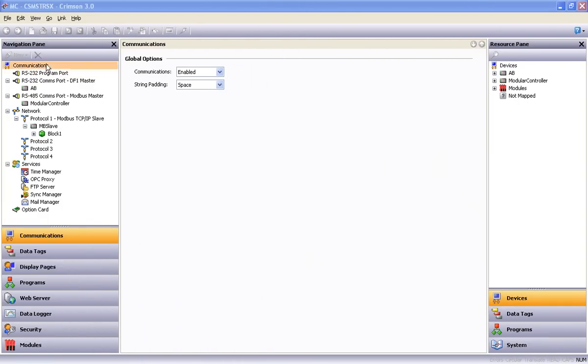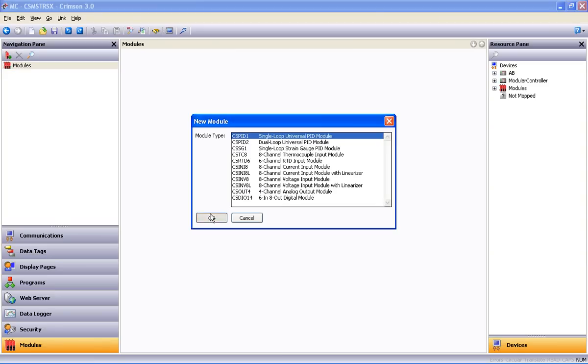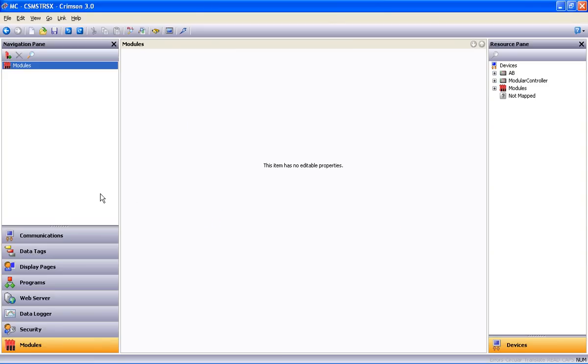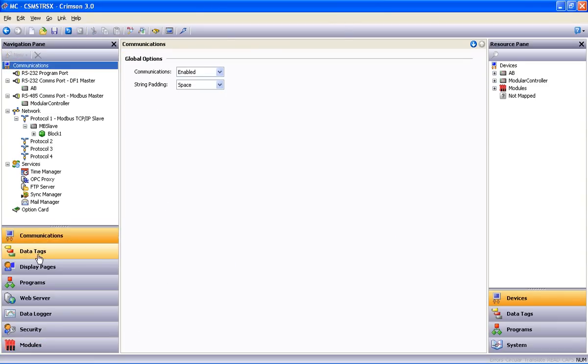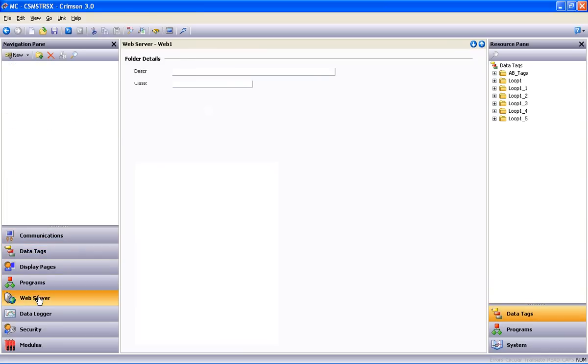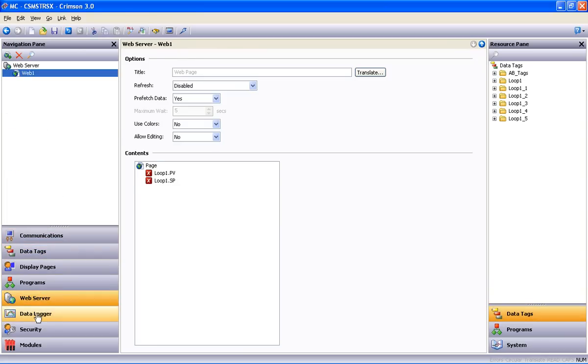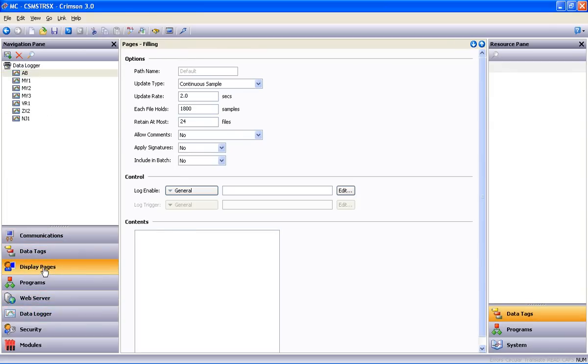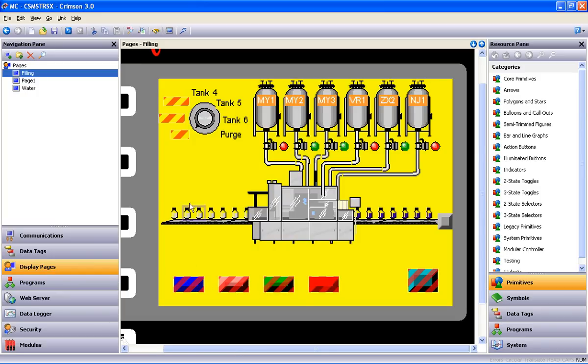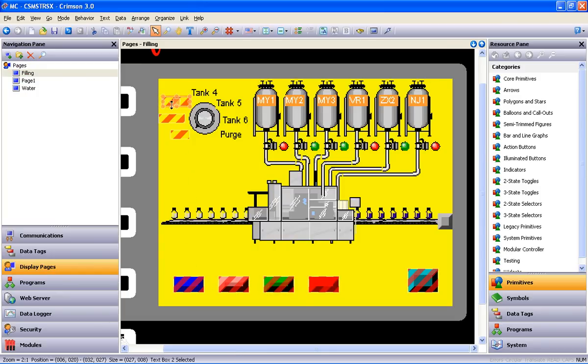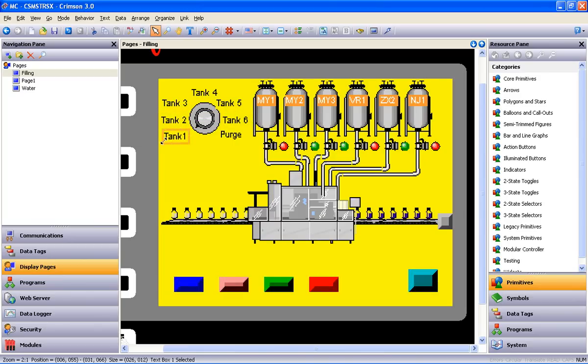So now our database is configured for a modular controller, and I can add the IO I need to suit the application. Again, the communications devices, the data tags, the web server, and the data logger have all come along for the ride. And so did the virtual display pages, but you'll notice Crimson 3 has flagged a few errors for us to address. Because this time we converted from a higher resolution down to a lower resolution, some of the objects on the display may not be sized properly. In some cases, it may simply be a matter of resizing the text box by a pixel or two, like these selector switch labels.